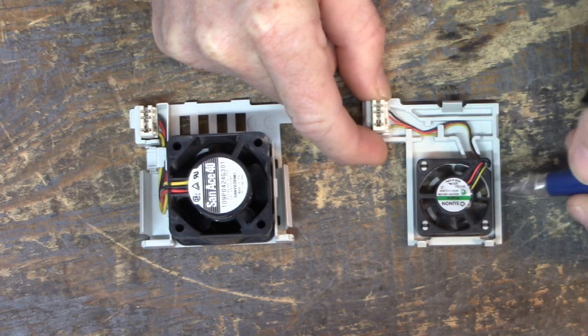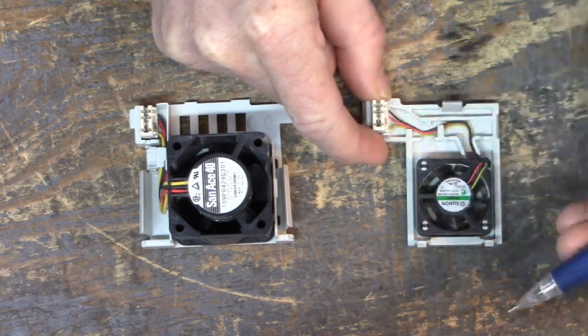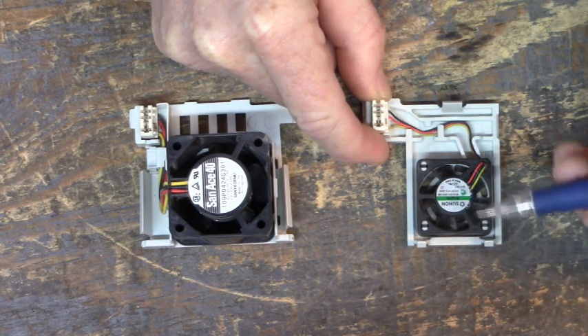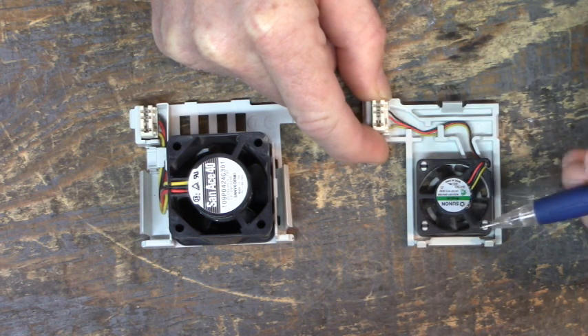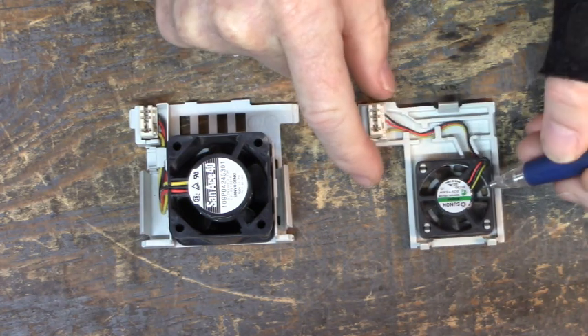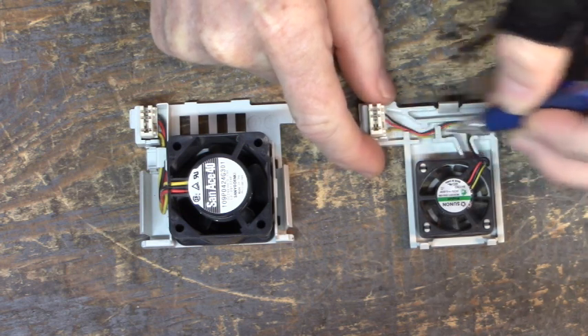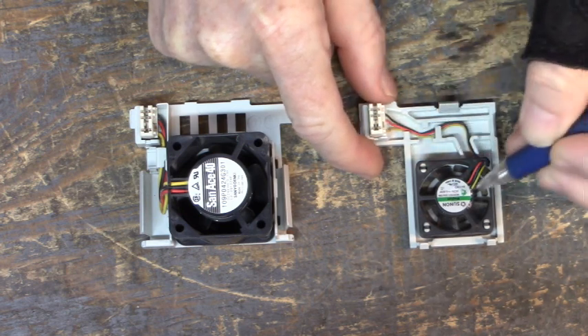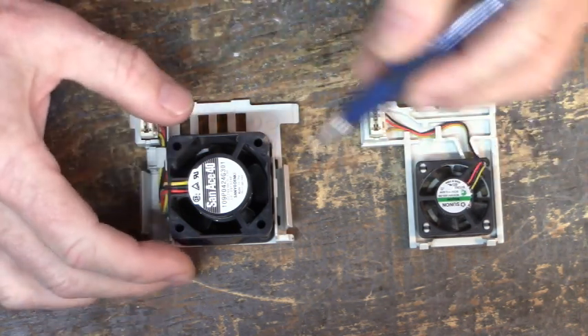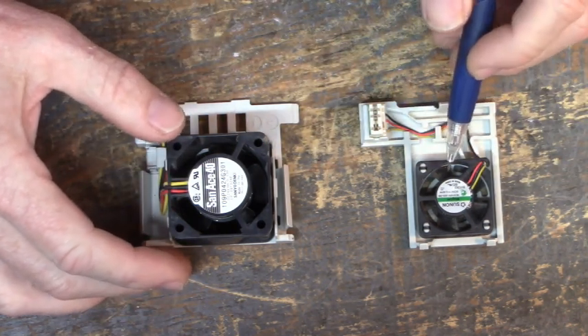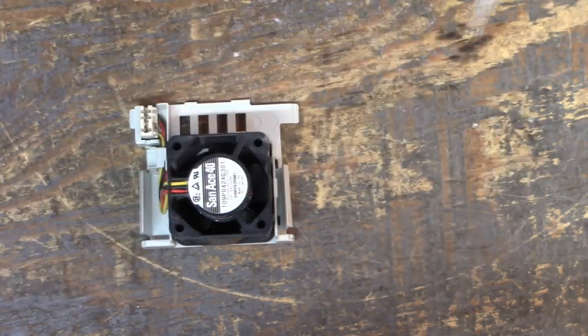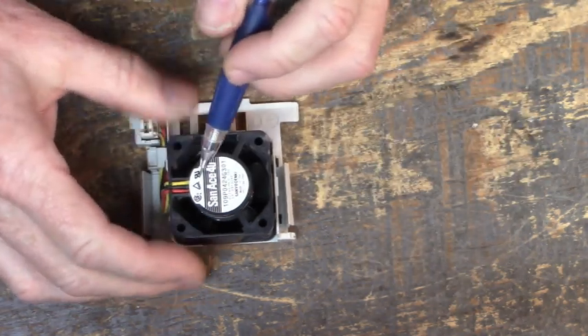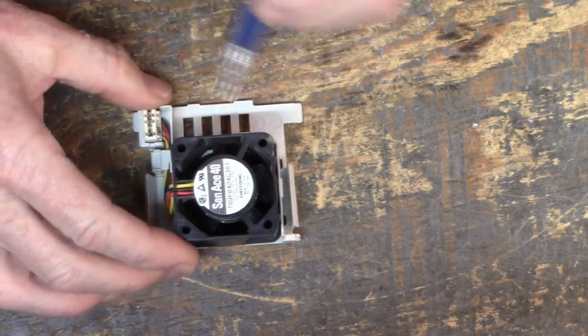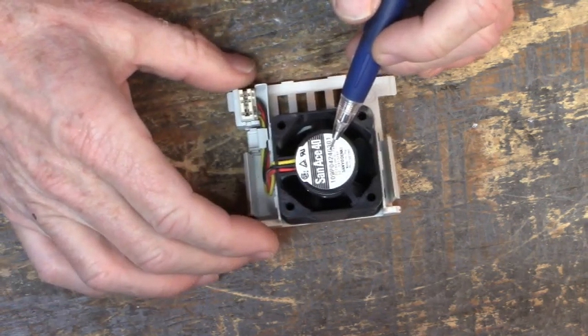Now some drives emit a square wave and some drives are just like 0 to 5, either at 5 volts it would be spinning or at 0 volts it would be spinning. And the ones that put out a square wave, that's obvious. You can see the square wave and the drive picks up that square wave and says, okay, we're going. Now this one is bad. We're not going to try to show you how that output works with that bad fan, but this one right here, we'll hook it up and we'll test it.